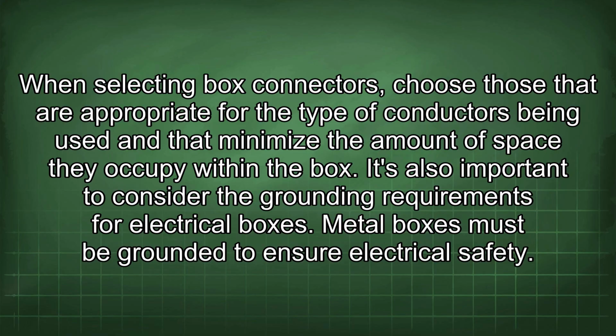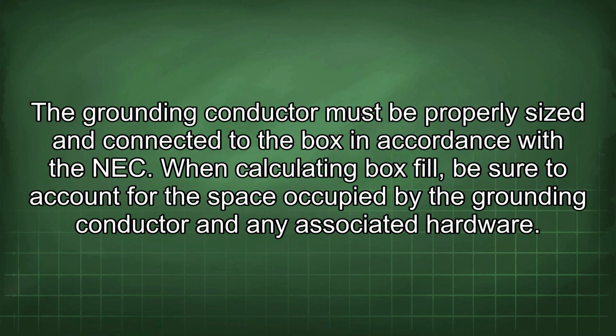Consider the grounding requirements for electrical boxes. Metal boxes must be grounded to ensure electrical safety. The grounding conductor must be properly sized and connected to the box in accordance with the NEC. When calculating box fill, be sure to account for the space occupied by the grounding conductor and any associated hardware.